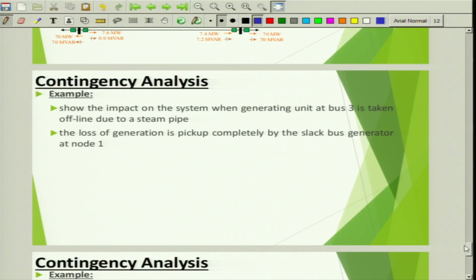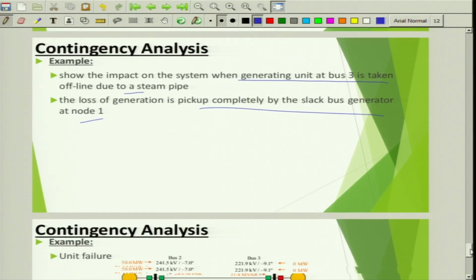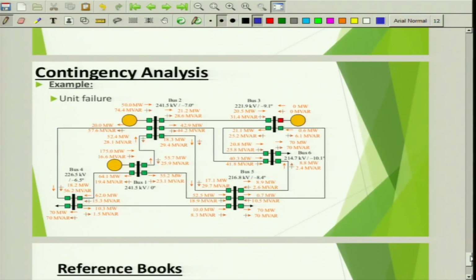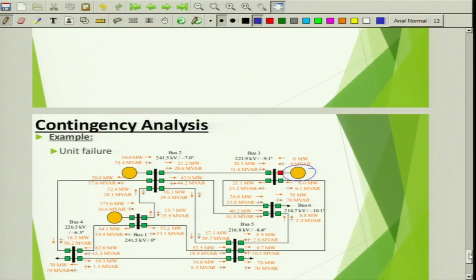Now another case, to show the impact on the system when the generating unit at bus 3 is taken off due to a steam pipe fault. There is some fault in the steam pipe and generator 3 is gone for some reason. The loss of generation is picked up completely by the slack bus generator, or bus node 1. I will just show you that. So this is the case. If there is a generator which was present, now it is not generating any power, and because of which there is a change at node 1, this one.